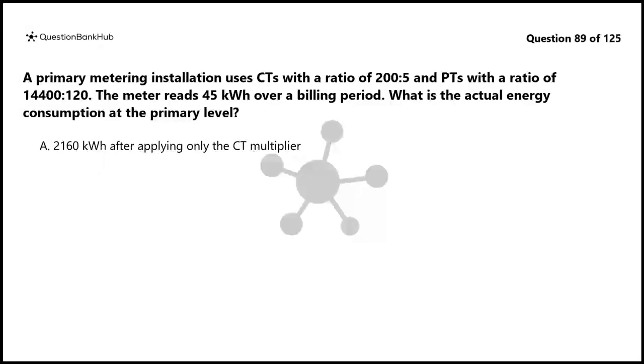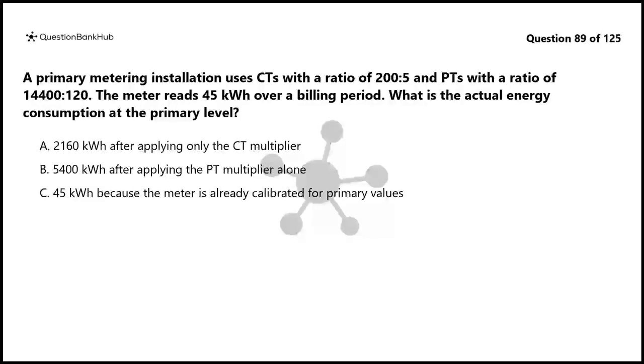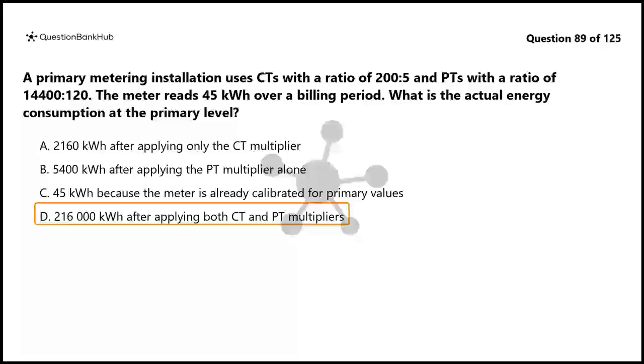A. 2160 kWh after applying only the CT multiplier. B. 5,400 kilowatt-hours after applying the PT multiplier alone. C. 45 kilowatt-hours because the meter is already calibrated for primary values. D. 216,000 kilowatt-hours after applying both CT and PT multipliers. The correct answer is D.